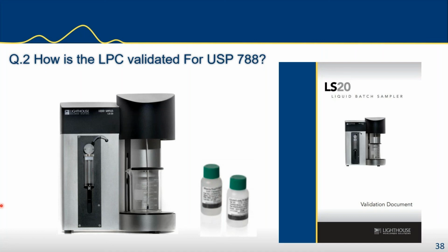So the basic validation requirements also include sample volume verification, the volume accuracy test, and sample flow rate verification. You also calibrate the sensor during the test. You also do a sensor resolution test using 10 micron test particles. For the count ratio test, you use the blanks test using clean particle-free water. And then the count ratio test that I've just explained using the 15 micron particles.